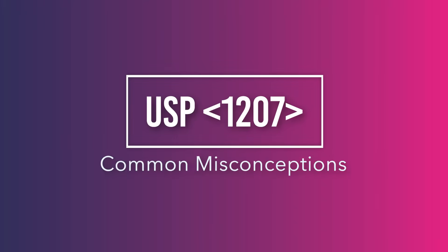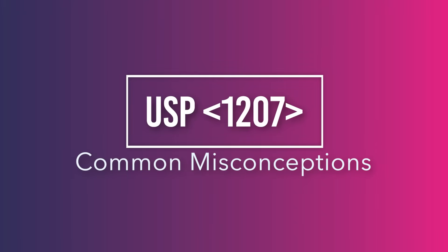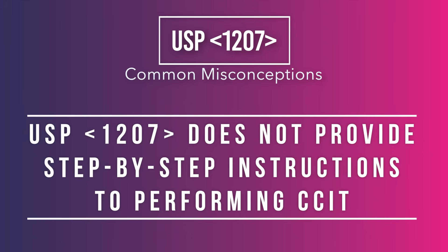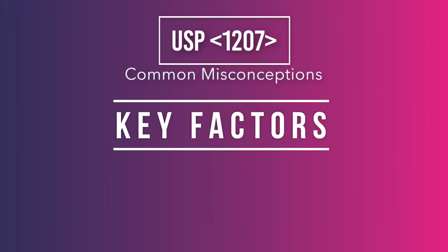To fully understand your USP 1207 CCI testing program, we must correct some common misconceptions. USP 1207 is a general information chapter that provides guidelines to be followed. It does not provide step-by-step instruction on what test to choose or how to operate the specific instrument being used. The selection of the optimal test method for a specific product and package system is dependent on a number of key factors.